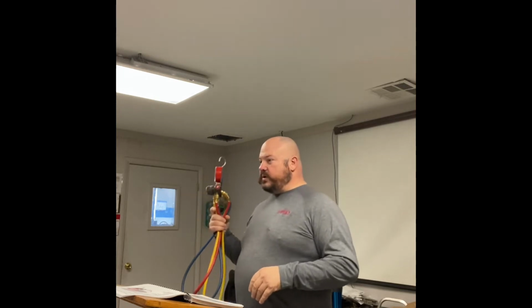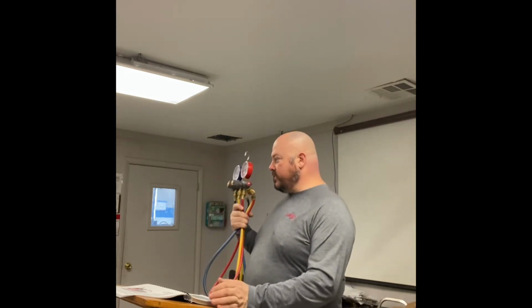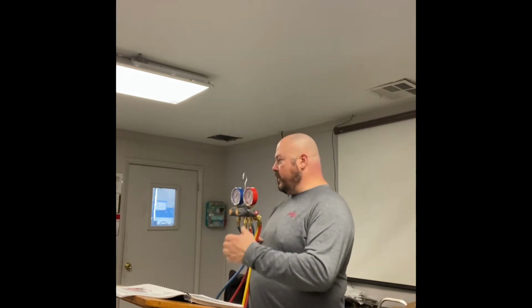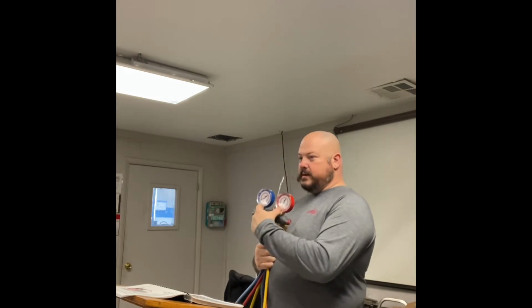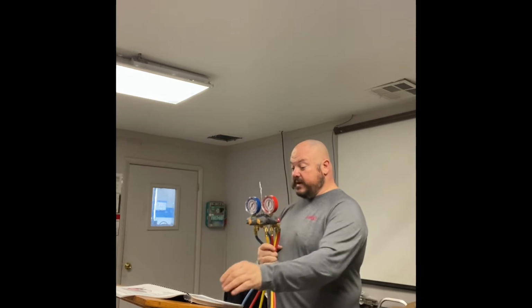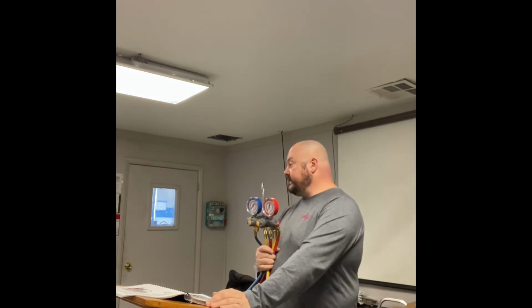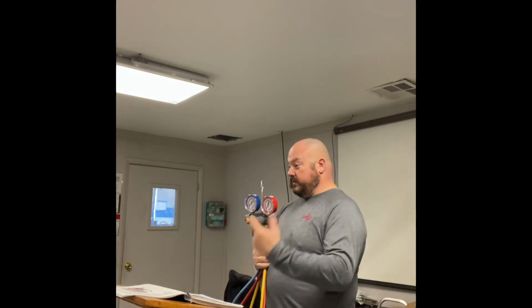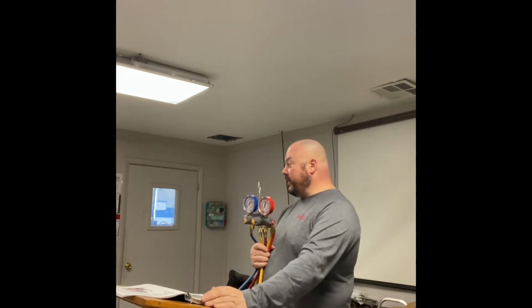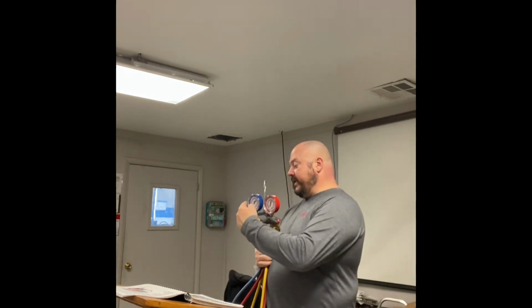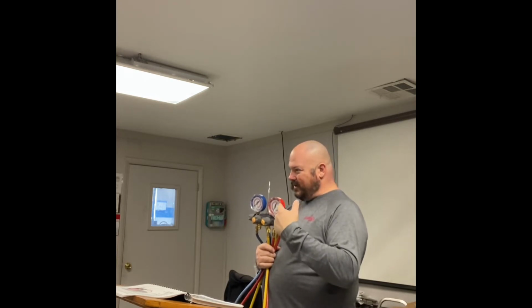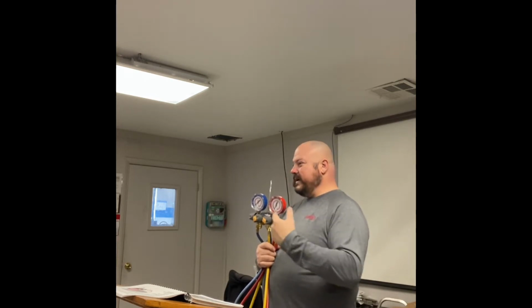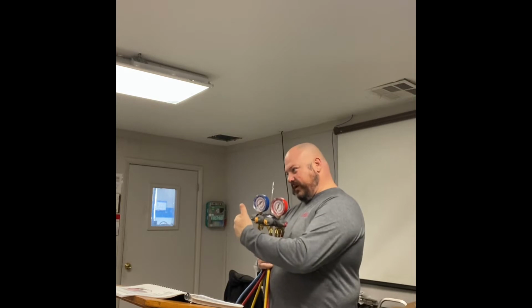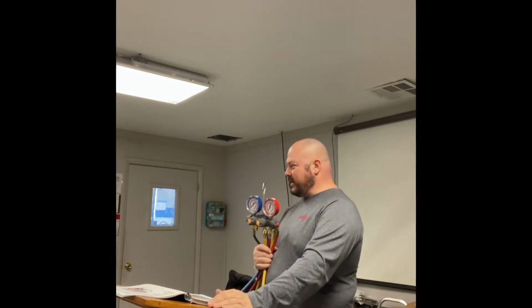So let's say you put 250 psi of nitrogen on that system. You're gonna watch both sides, okay? Because you have both hoses hooked up. You're gonna look at both sides, and if your high side starts going down, and then maybe your low side starts going down, you know it's on the high side. Look on your liquid line. Vice versa, if it's doing it on this side, look on your suction side.